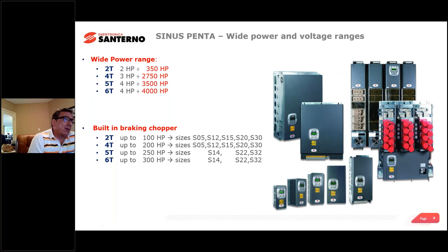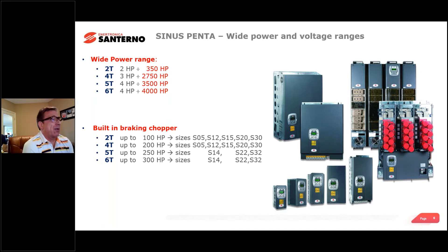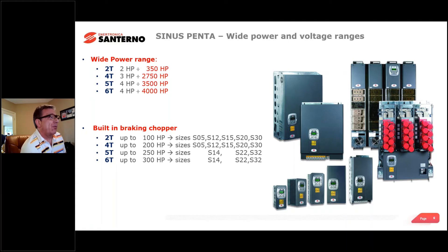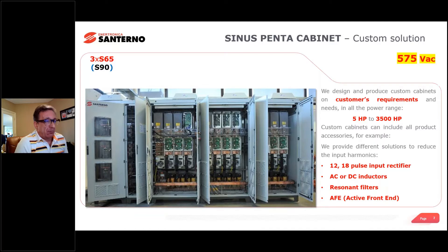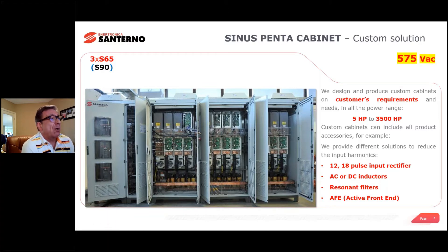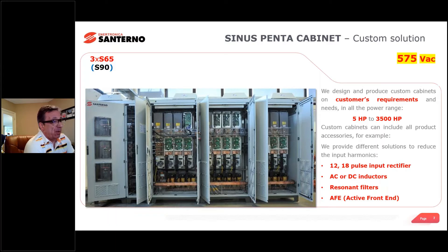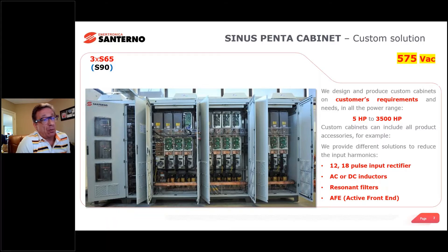Having a product capable of 690V means the power electronics can withstand line swells. We have a very large power range within the product — up to thousands of horsepower at 600V. For punch pressing, mill processing, or any eccentric loads, a built-in brake chopper is important — the ability to take excess energy from a punch press or rapidly stopping crane and dispel it through a separate circuit, sometimes called a seventh transistor. Good manufacturers should also be capable of packaging the product into large, complex cabinetry for multi-pulse or active front end harmonic solutions.